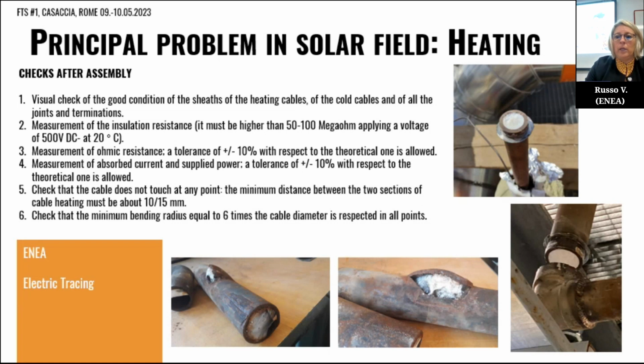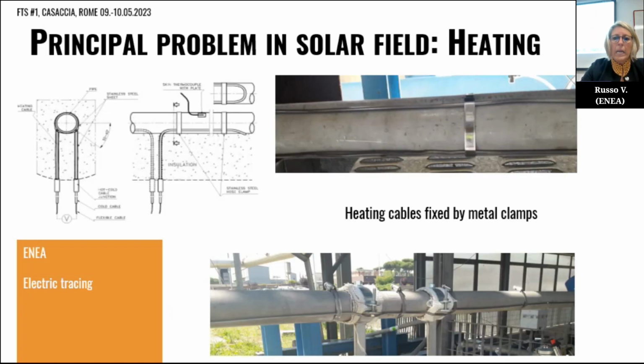Here are some pictures of piping with solid salt inside. This occurs when the heating system doesn't work properly or isn't installed in the correct way. Now we can see how to install the electric cable, in this case along the pipe. Here is the scheme of how to fix the cable around the pipe. The cable must be fixed by metal clamps. And then there is a skin thermocouple, which we can see here, used for the control of the temperature of the cable, the tracing tape cable. Obviously, the thermocouple must be installed at the coldest point.